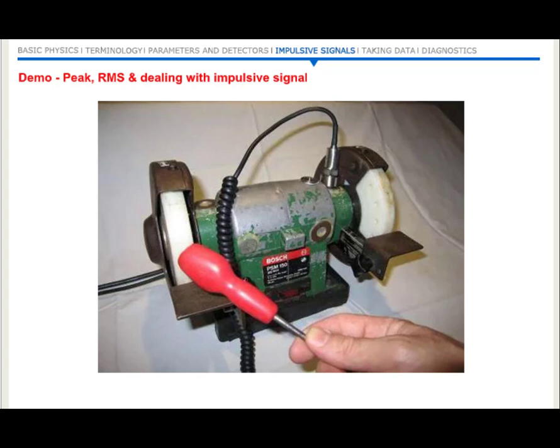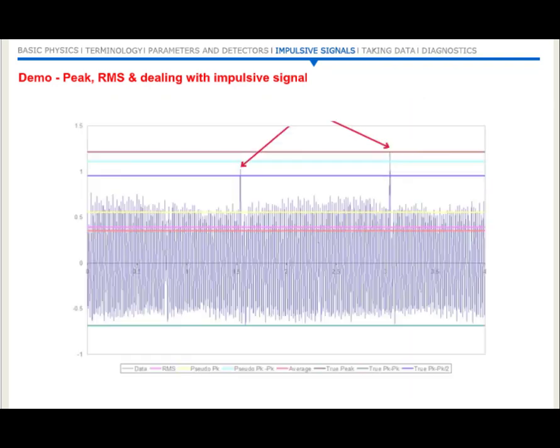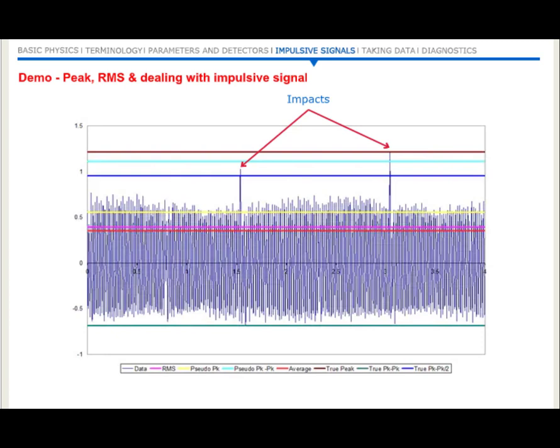Impulsive signals result from impacts. As an example, consider what happens if we use a screwdriver handle to tap this bench grinder as we collect vibration data using an accelerometer mounted on one of the bearings, as shown. Here we see the resulting time waveform. During the time taken to collect this data, the machine was struck twice with the screwdriver handle. We can see the two spikes in the signal that resulted. The effect of these two spikes on the RMS level of the signal will be very small as a result of the averaging that occurs in calculating the RMS value.